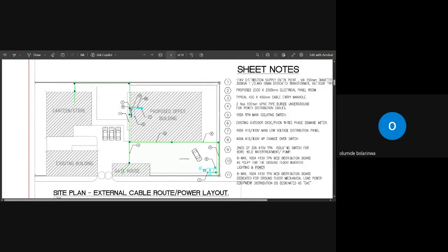If you see any specification of a transformer that says ONAN, it shows that it is being used externally. We have indoor transformer and we have the outdoor transformer. Any transformer with an ONAN description, it is called what? Indoor, outdoor. That's why they call it oil natural, air natural. Now we have different brands of transformers in this case. We have the likes of Nexan, we have the likes of ABB, we have the likes of Beta in this case.